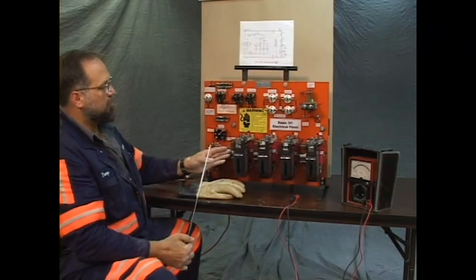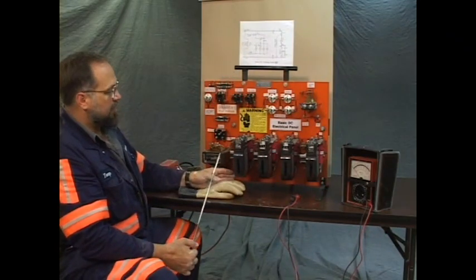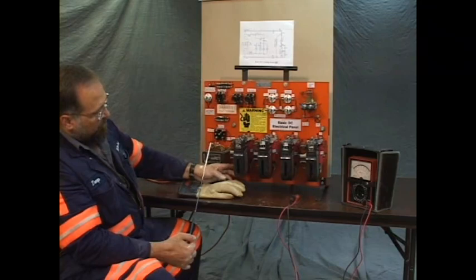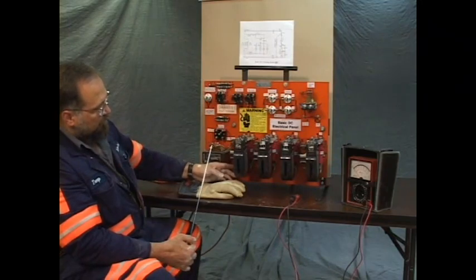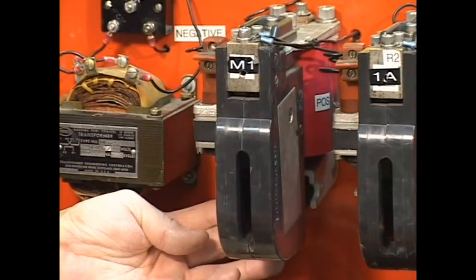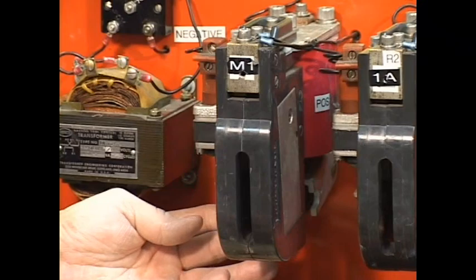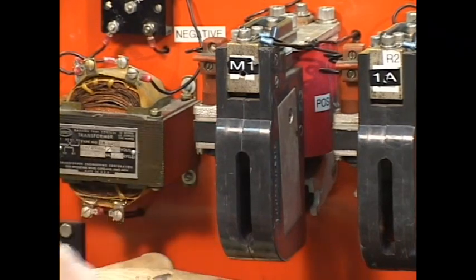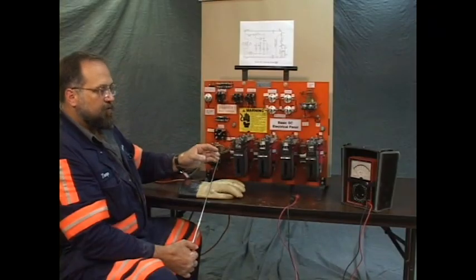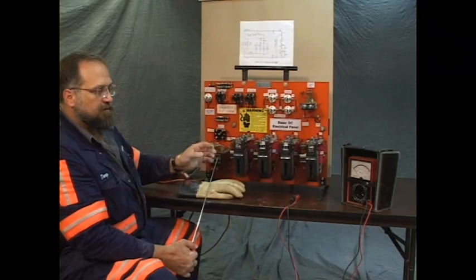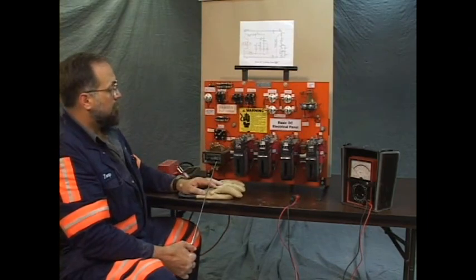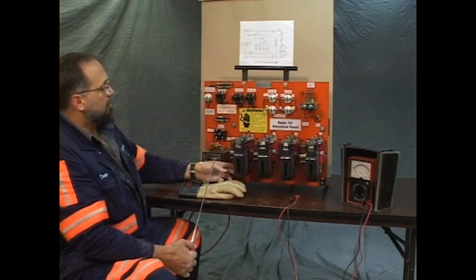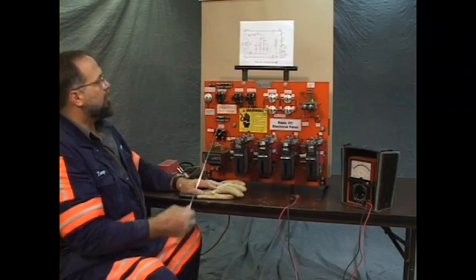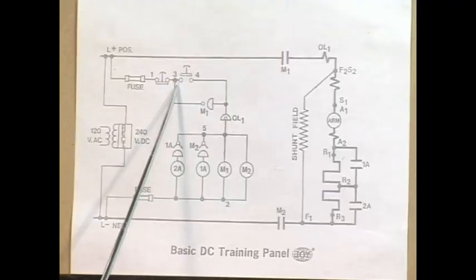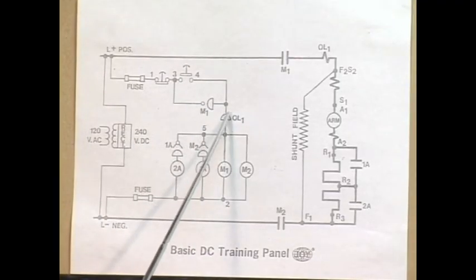As soon as this coil is energized, magnetized, this little bar bolted onto the side of the movable portion of the contactor transfers that magnetic energy to the mercury tube, draws the mercury inside the tube into the contacts, and completes the circuit. Well, that may indeed be happening, but for whatever reason, it's not completing the circuit.